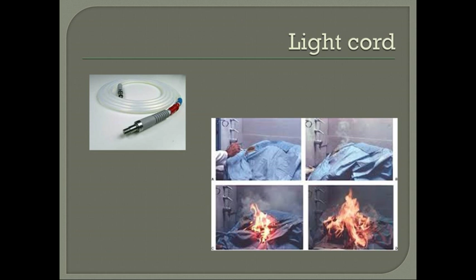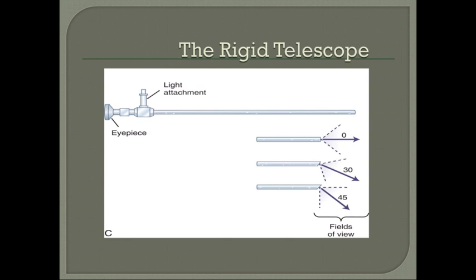The rigid telescope is a lens that captures the image illuminated at the tip. It comes in 0, 30, 45, and 70 degree angles. Always hold the scope by the head, not the shaft. You can bend it. Use lint-free cloths to clean the scope so you don't scratch a lens. And the optical angle is the direction in which lenses are focused on the image. Telescopes are delicate and expensive, and it's the responsibility of the surgical technologist to handle and maintain the telescope.